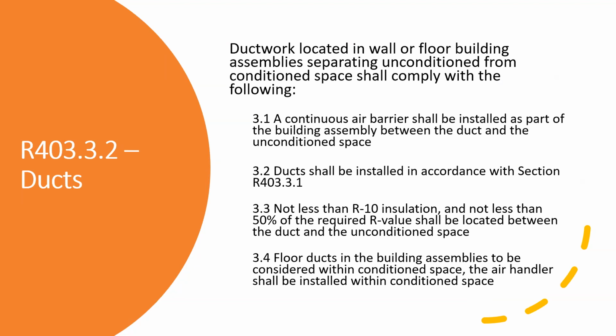It also needs to have insulation separating it from being in contact with that radiant barrier roof decking, or just OSB or zip board or anything considered a roof material. It should not be in direct contact. So a continuous air barrier shall be installed as part of the building assembly between the duct and the unconditioned space. That usually already happens. The duct shall be installed in accordance with the section that talks about duct installation and the duct R value. Then it says not less than R10 insulation and not less than 50% of the required R value shall be located between the duct and the unconditioned space. So that's the exterior or the attic.